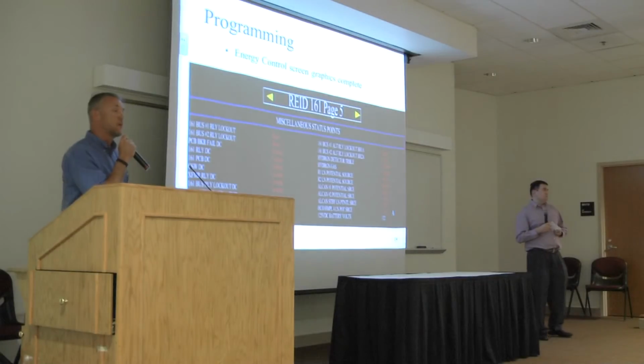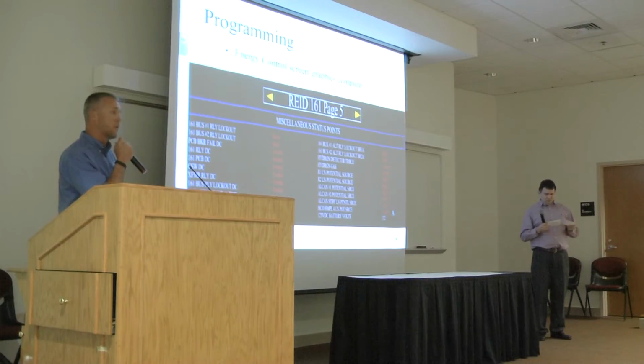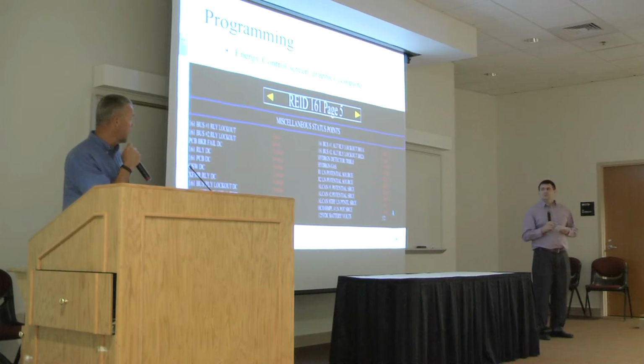This is an actual screenshot that the operators in our dispatch energy control see. The red arrows depict what were the additions for the ground alarm that show whether they're in normal or alarm. That would also generate an alarm on their alarm page. In the far right, you see the actual voltage, which is actually displaying, and system checkout performed perfectly, and representation of the actual field conditions of the display unit and the OSI screen at dispatch were perfect.